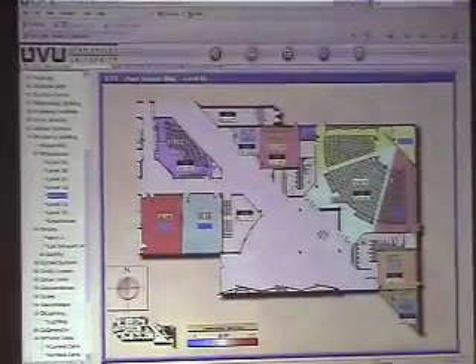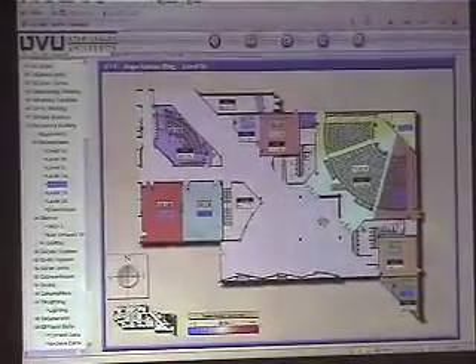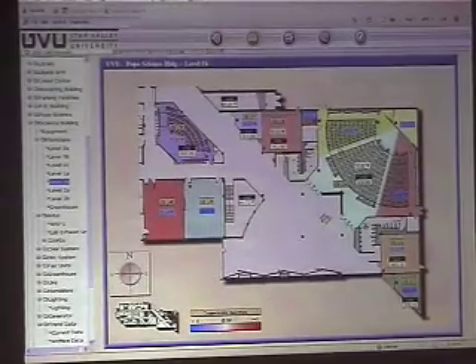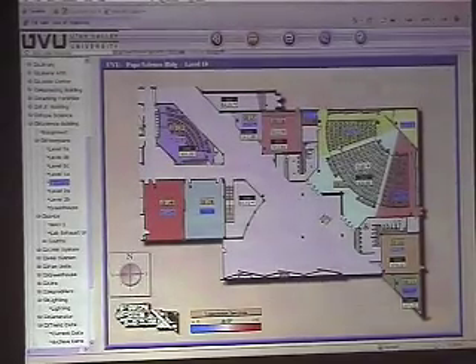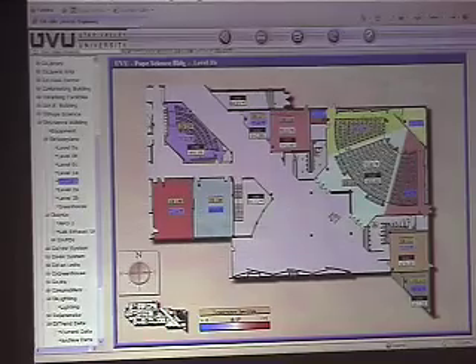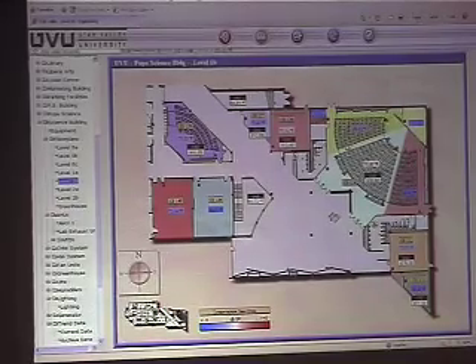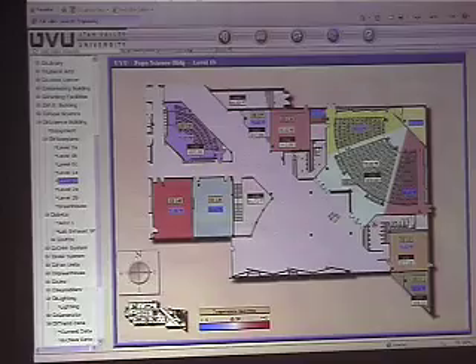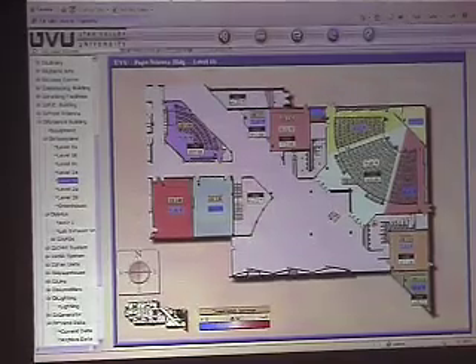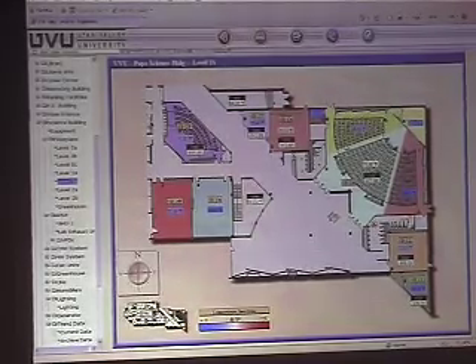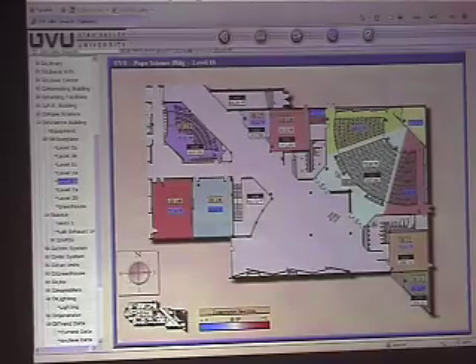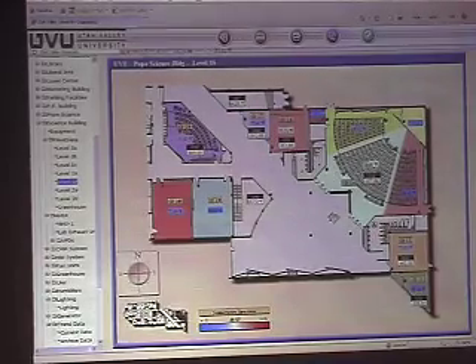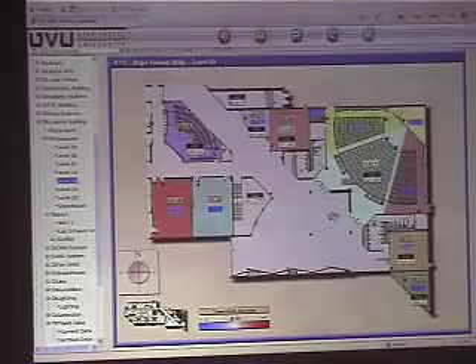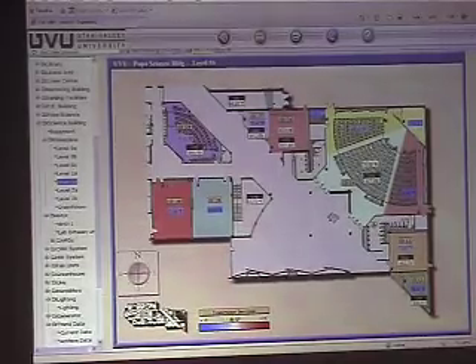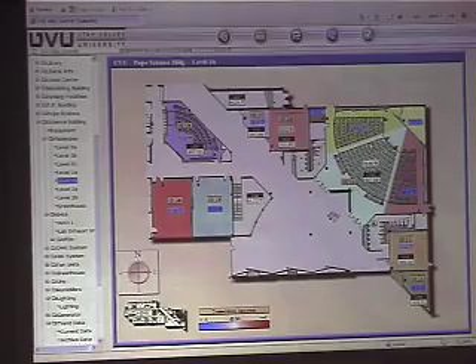This is the lecture hall I was talking about that's resetting the duct static pressure. This one has three large VAVs in it. We monitor the damper position, so if it gets above 90% as that ramps up, the loop will reset that static pressure up to 2.5 to try to bring that back down. This is the only area that fell short on air. Everywhere else in the building, they were able to achieve flow with 2 inches.